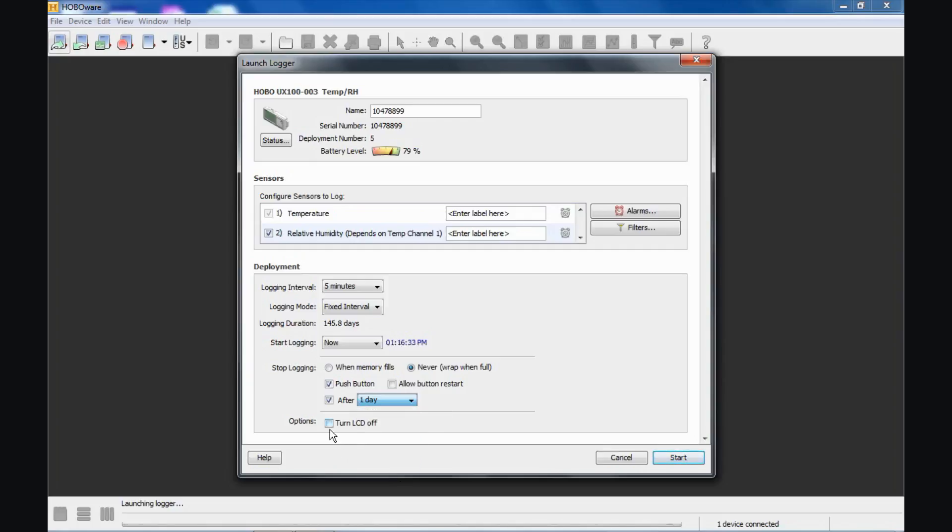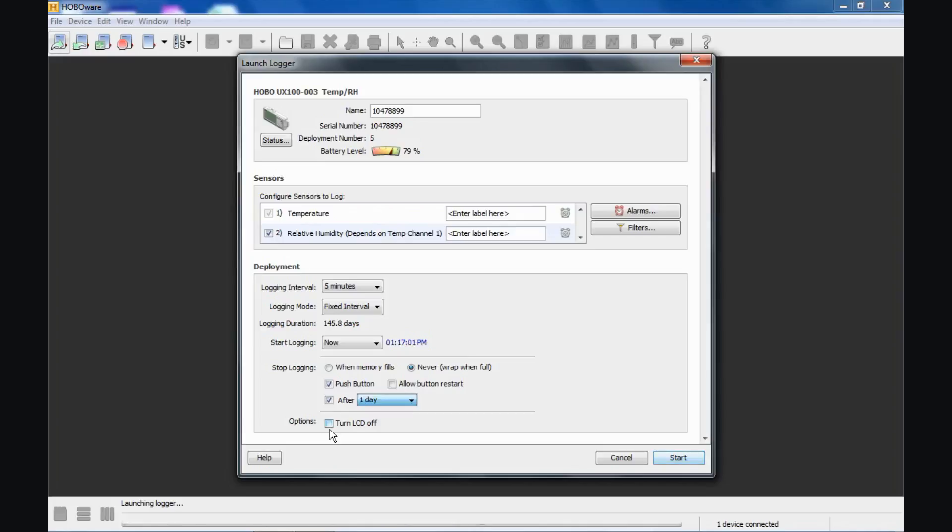There is one more option, you can turn the LCD display on the front of the logger off, you can choose to do that. This saves a little bit of battery life. It also makes the logger appear that it is not doing anything to the casual user. It also hides the data from—in case you do not want anyone to know what the current temperature or relative humidity is in the area being monitored. You can turn that LCD back on just by pressing the button on the top of the logger and that will stay lit for 10 minutes and then it will go blank again.